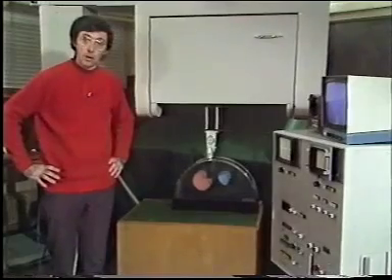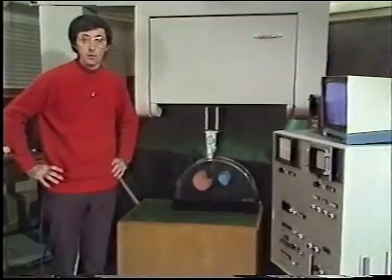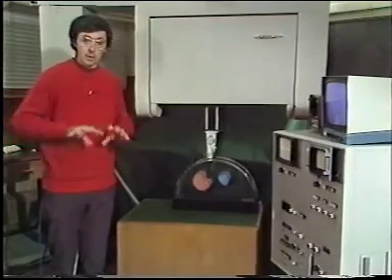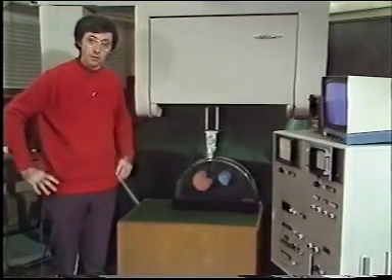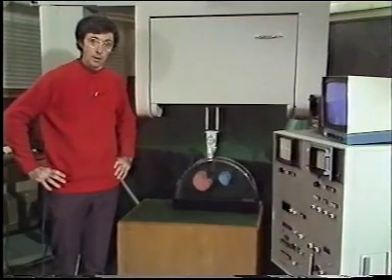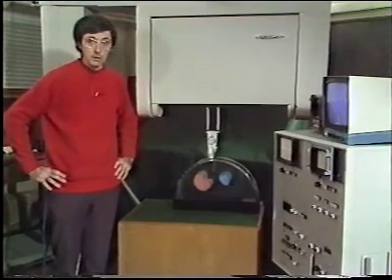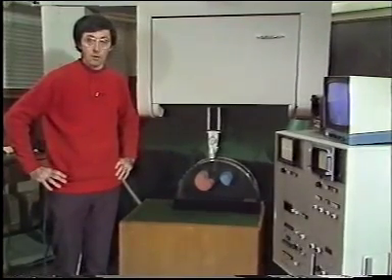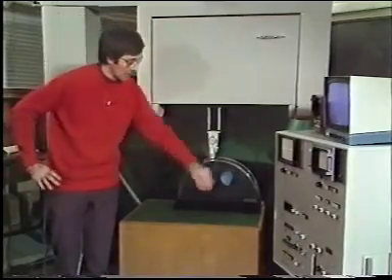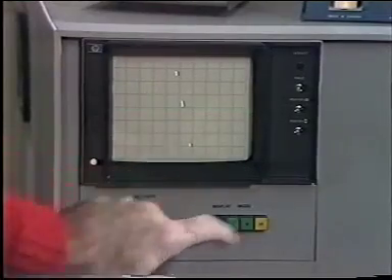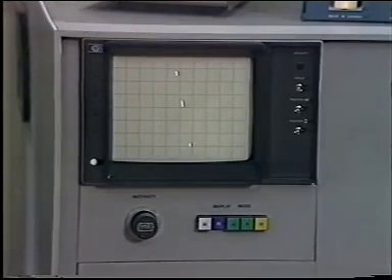The A scan is a simple echo ranging device, but in the case of the human fetus, we want information about the shape of the whole reflecting surface, so we use a different type of scan. It's based on the so-called B scan, in which the brightness of the trace is modulated by the reflection. If I press this button, we can get a B scan, and here you can see the brightness is brought up in the two places where there was a reflection.